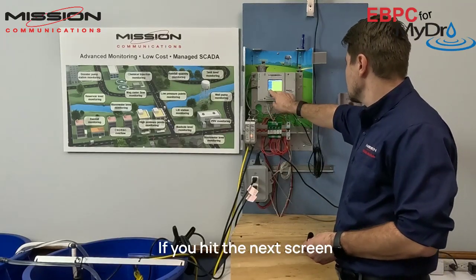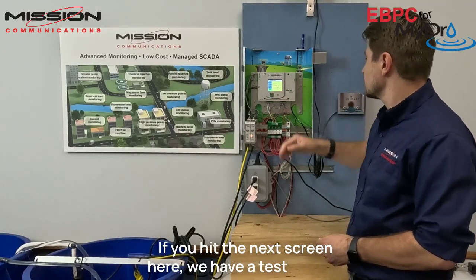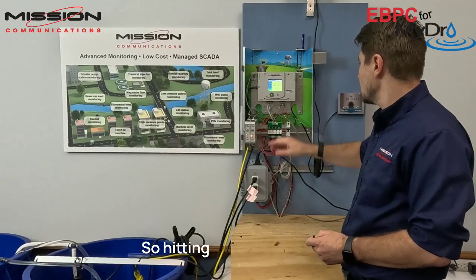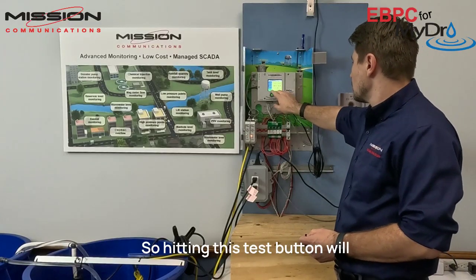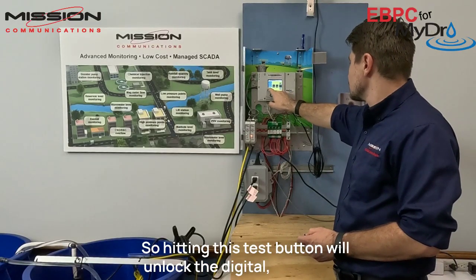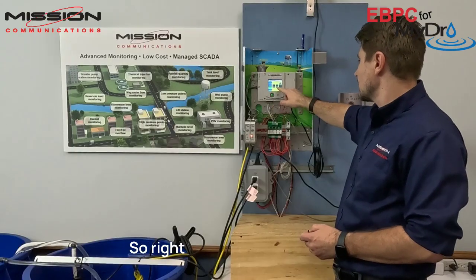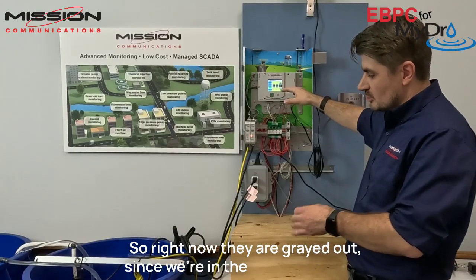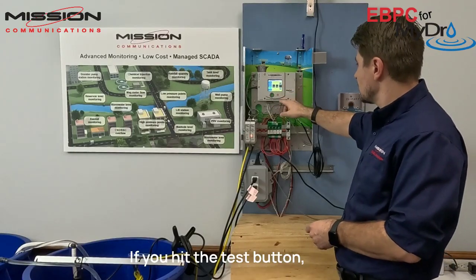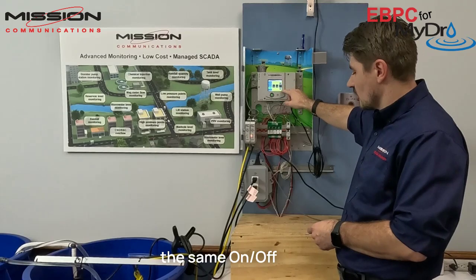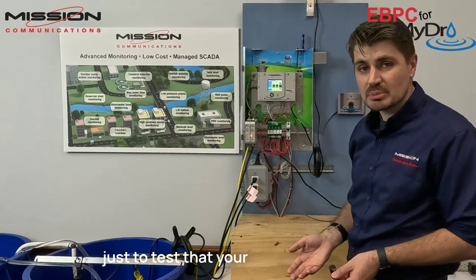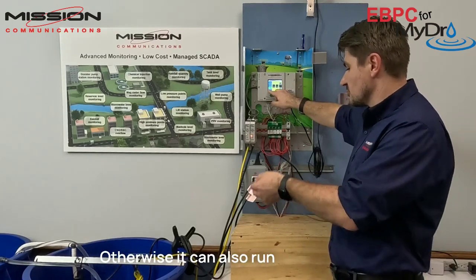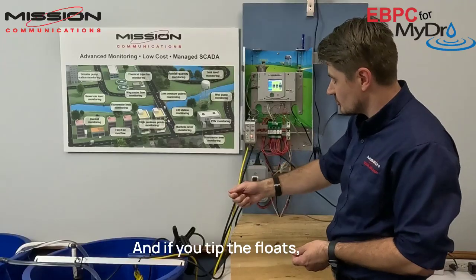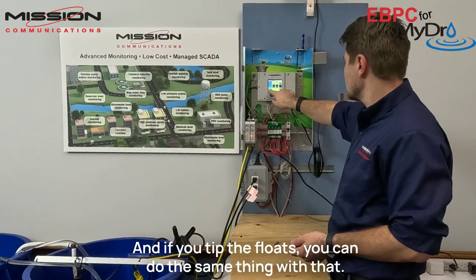If you hit the next screen here, we have a test screen. So hitting this test button will unlock the relays. So right now they are grayed out since we're in the pump controller. If you hit the test button, you get the same on-off option just to test that your pumps are working. Otherwise, it can also run through a cycle. And if you tip the floats, you can do the same thing with that.